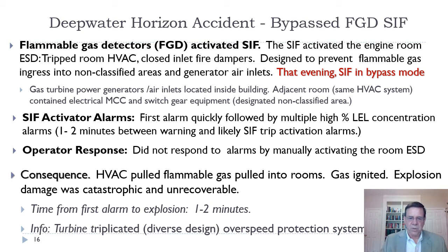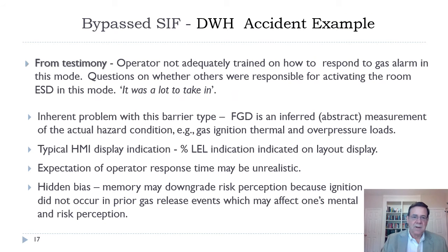And now, on the effect of the generators, they had triplicated overspeed protection, and here is another societal element: regulation may have been a contributor as to how all of these could have failed, and it may have been attributed to the requirements of how they do annual checks of these. The operator's testimony claimed they weren't trained on how to respond to the alarms, and didn't seem aware that there was a response to manually activate a shutdown function. There were questions about whether a person in a drill shack should have activated this alarm, and it's clear that it wasn't clear who was doing what.